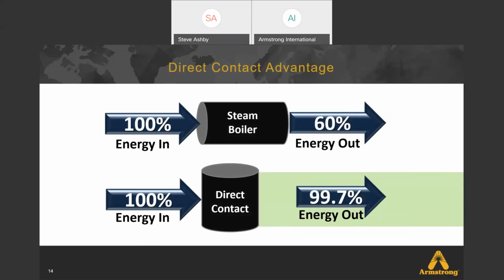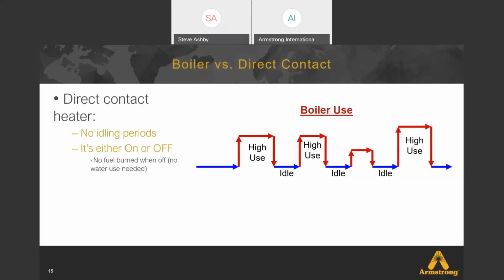With your 100% energy in on your steam boiler, again, a 60% efficiency. We give the same amount of energy to generate hot water by direct contact. We're almost at 100% efficiency. Direct contact heating, there is no idling. It is either on or off. Compared to a steam boiler where the demands fluctuate throughout the day, there's a lot of high use and go to an idle time, and that repeats itself throughout the workday.